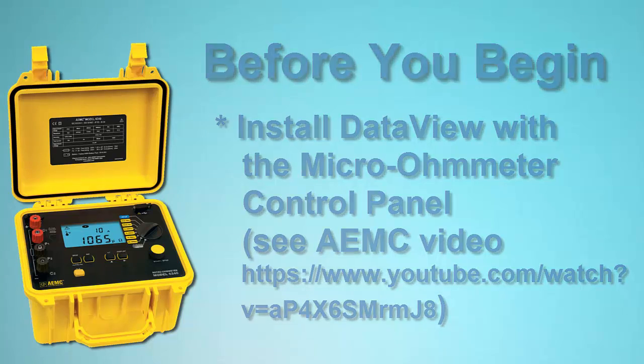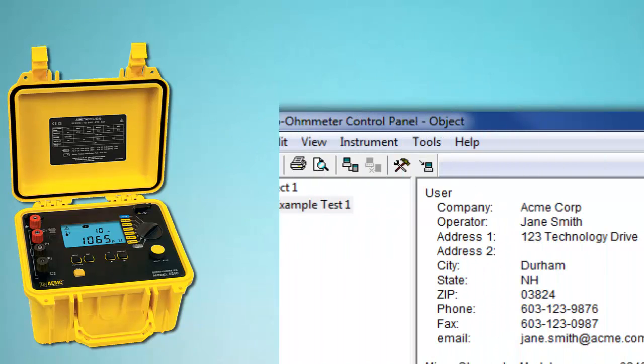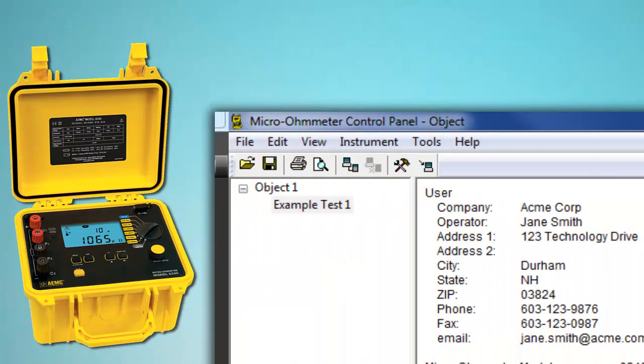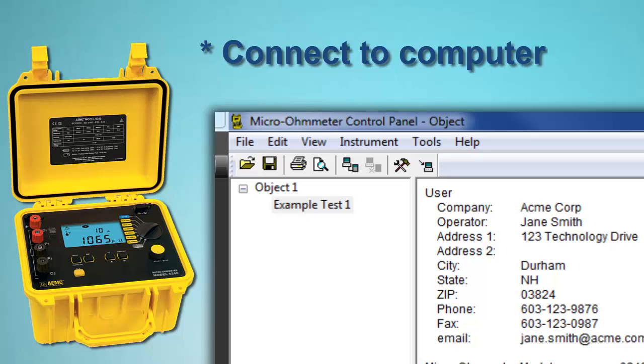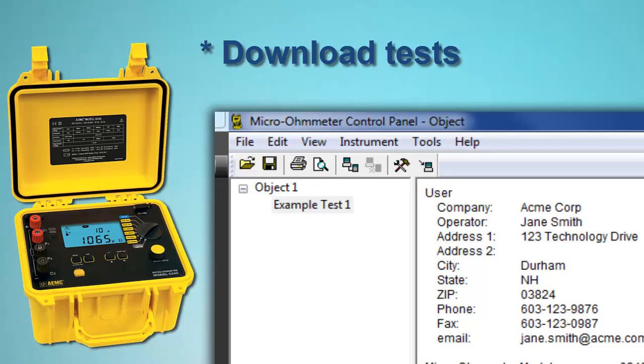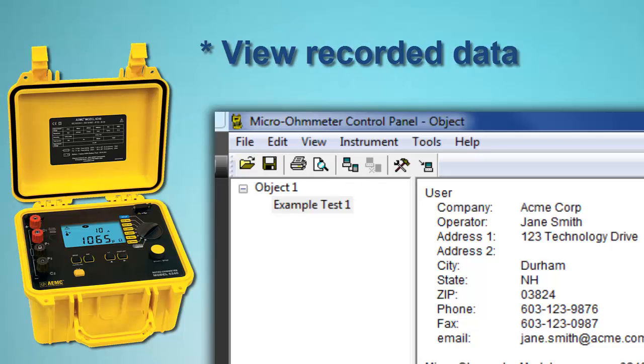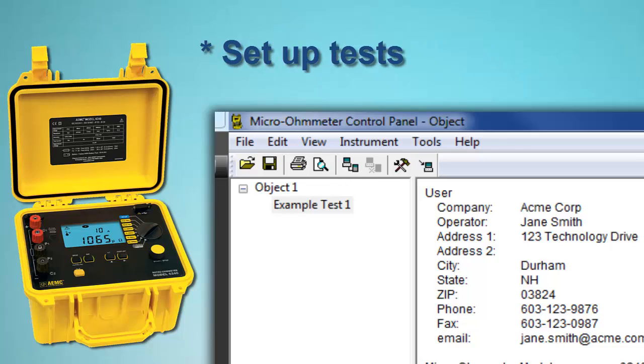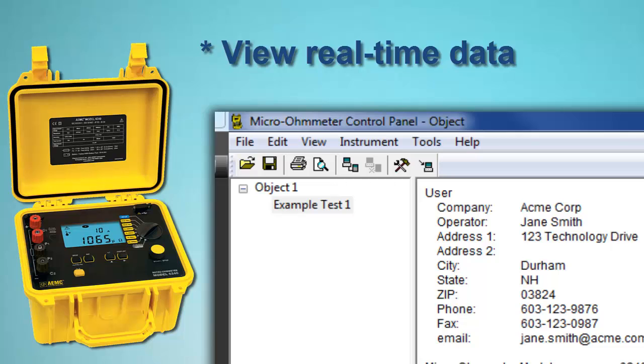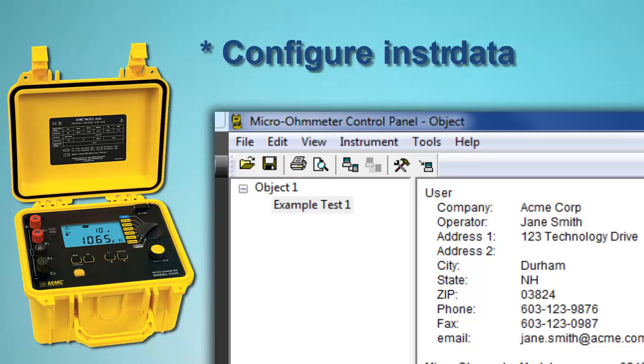The DataView Micro-Ohmmeter Control Panel is the primary interface for connecting with the Model 6240, downloading test results, and viewing the data on the screen. You can also use the Control Panel to set up tests, view measurement data in real time, and configure the instrument.